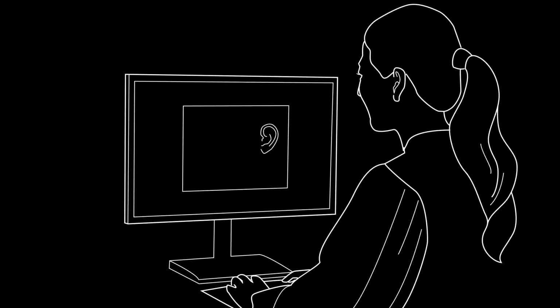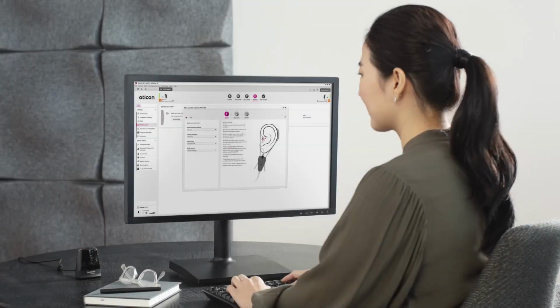When performing real ear measurements, it is important that the hearing care professional positions the probe tube correctly in order to get accurate measurements. Research shows that if the placement is off by as little as 2 mm, it can cause level changes of 2 decibels or more.